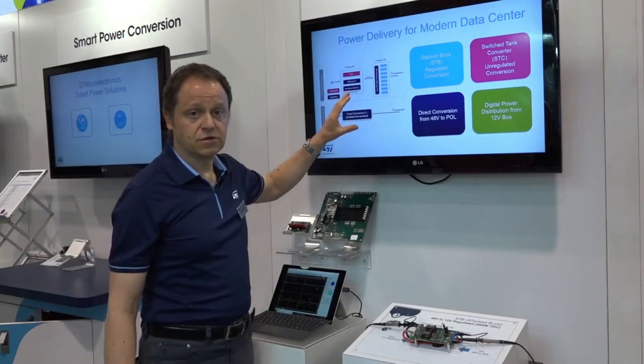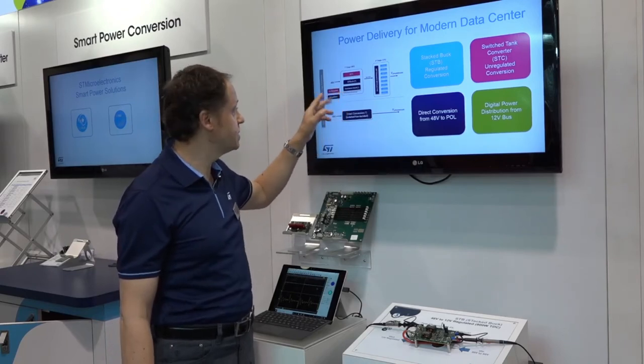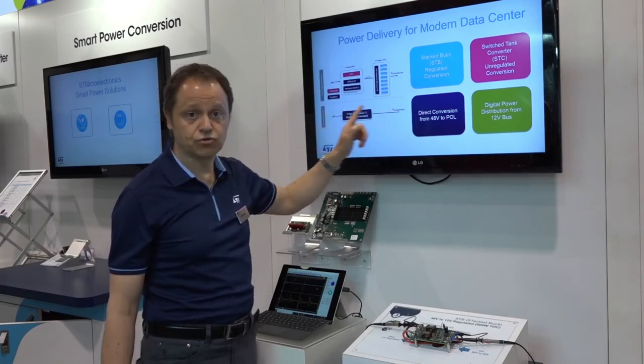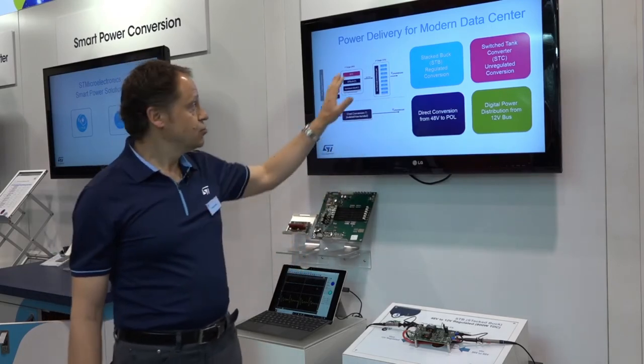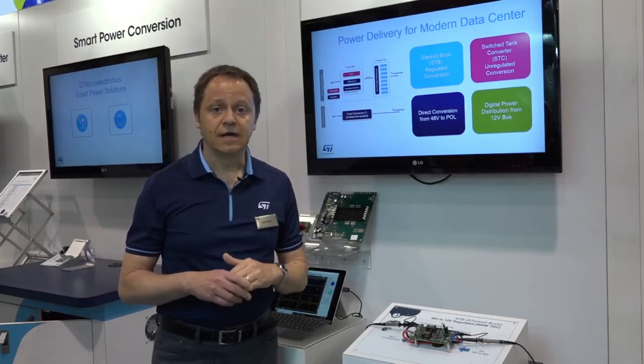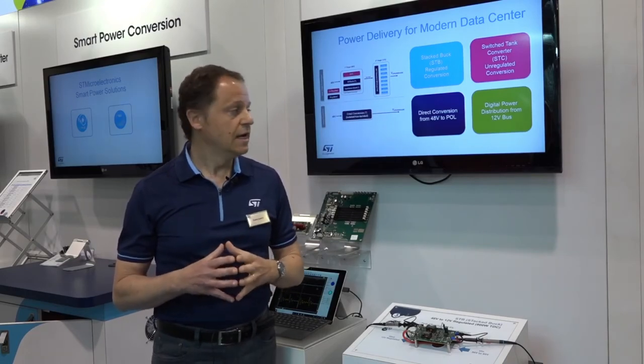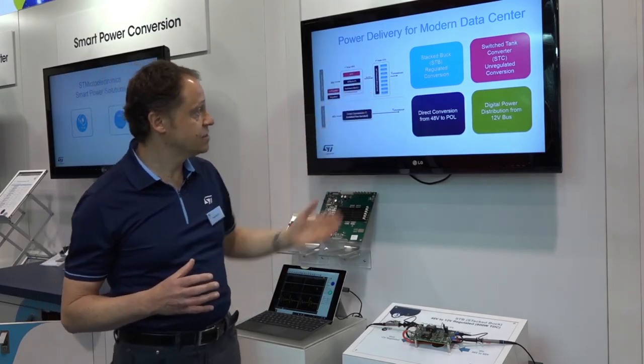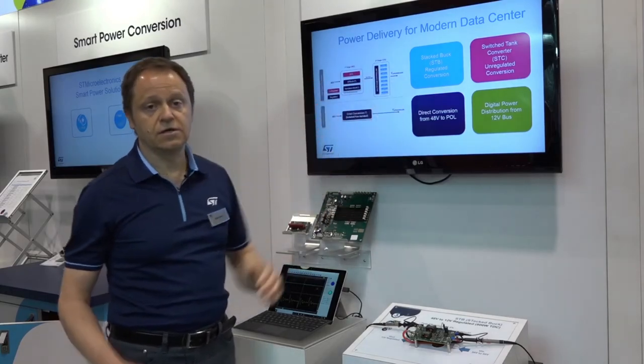The other class of products or architectures we have are transformer-based, and they can serve both the intermediate bus conversion or the direct conversion straight from 48 volts down to the CPU. The usage of these topologies maximizes system efficiency, power density, and overall power distribution using off-the-shelf components. The goal is to maximize the efficiency of the whole system from 48 volts down to the point of load.